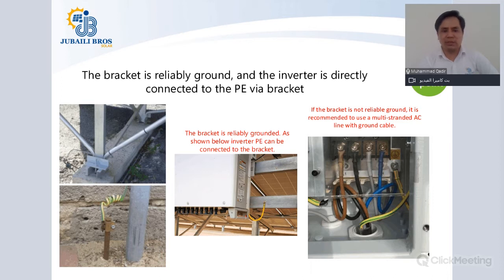Having multiple scenarios in mind, if we speak of the ground mount where you have large arrays and you have a big space at the back side of your tables to install the solar inverters, you can install your solar inverter in that location, and that's very good because it provides a shade to the inverter as well. And if your tables are properly grounded, then in such ground mount scenarios, you can use the outside earthing point of the solar inverters and connect to the frame on which the inverters are tied to.